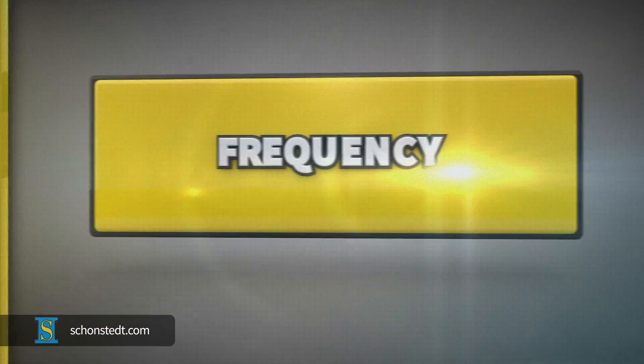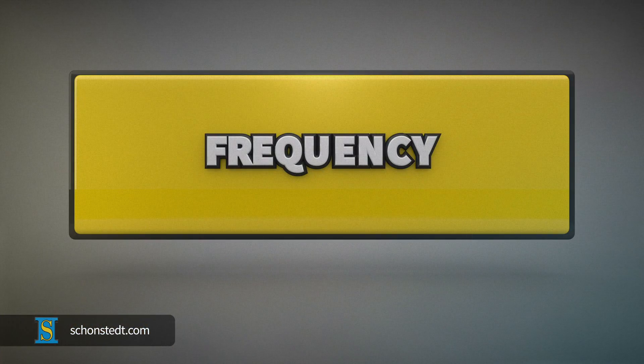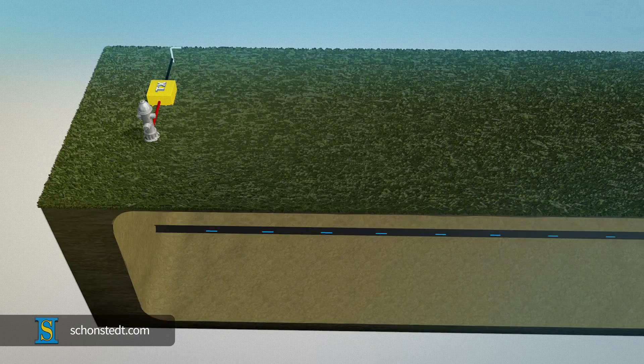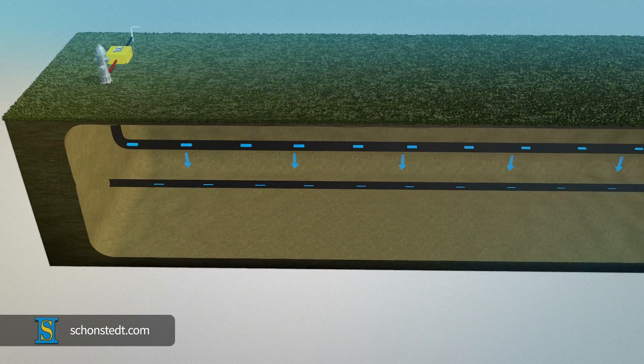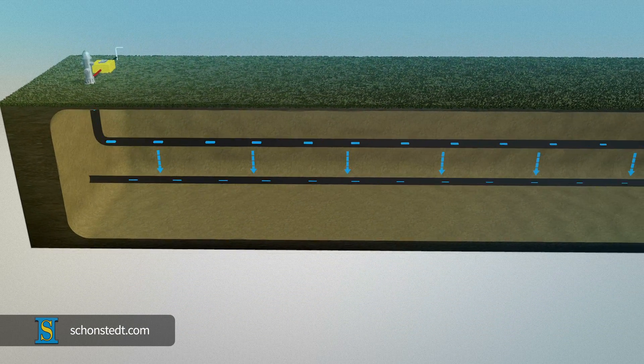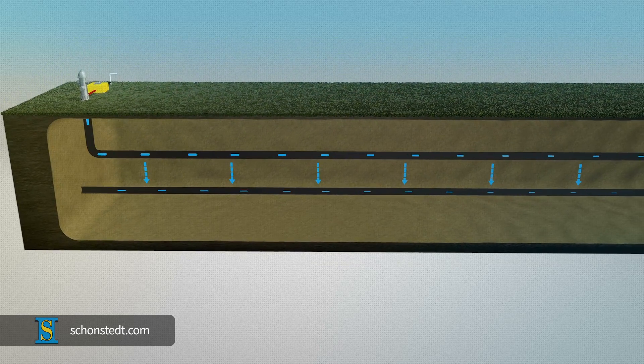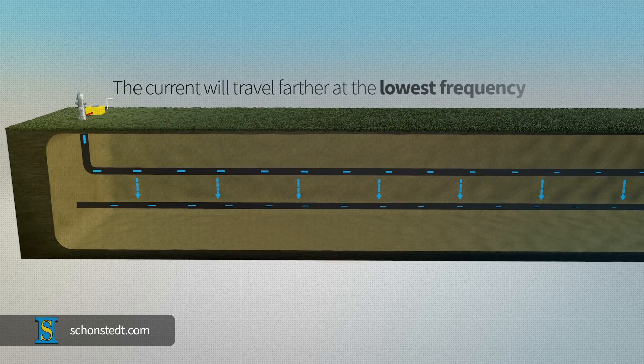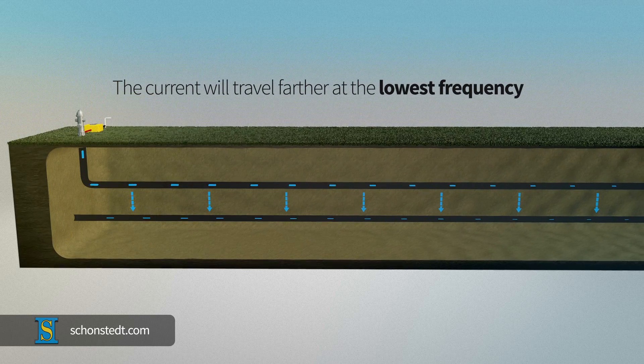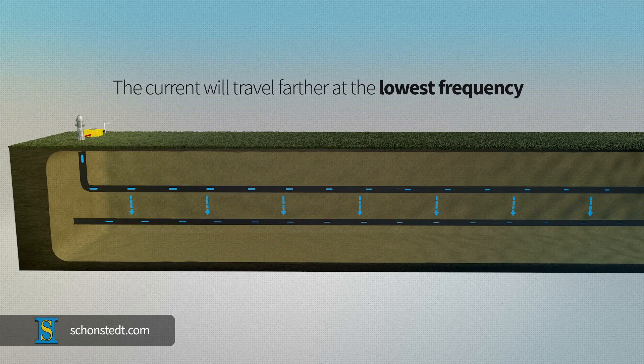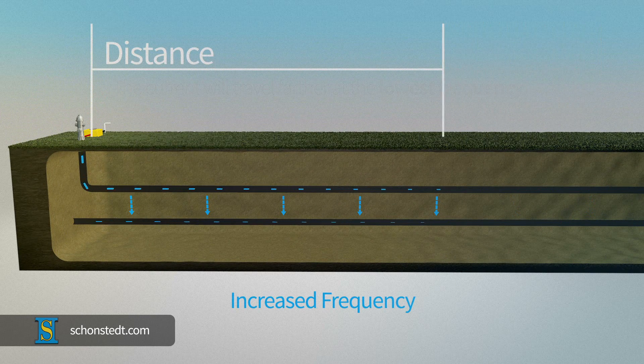One of the keys to getting a good signal is applying the proper frequency. If conditions are good – good conductor, connections, and soil conditions – the current will travel farther at the lowest frequency with less leakage to adjacent structures. An increase in frequency will cause the signal to leak sooner and cover less distance.